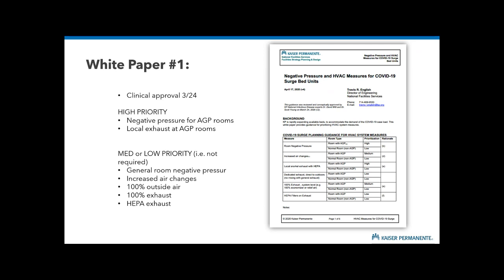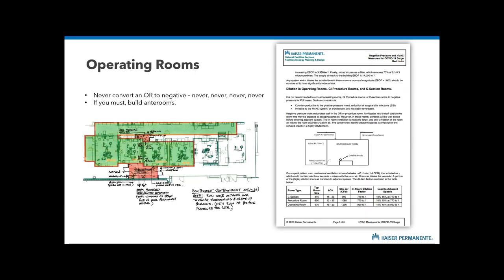We made it very clear that negative pressure is not required unless there's a room designated for aerosol generating procedures. We made it clear 100% outside air and 100% exhaust air are not required for surge units. HEPA filtering of exhaust and return is not required for surge units. We made it clear never convert an OR to negative pressure.